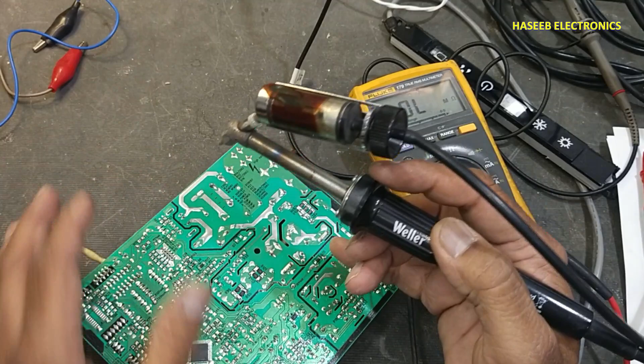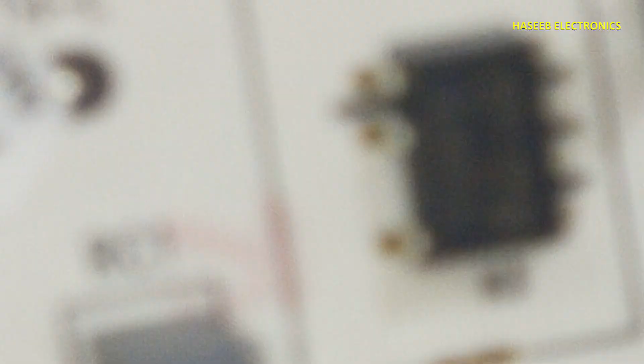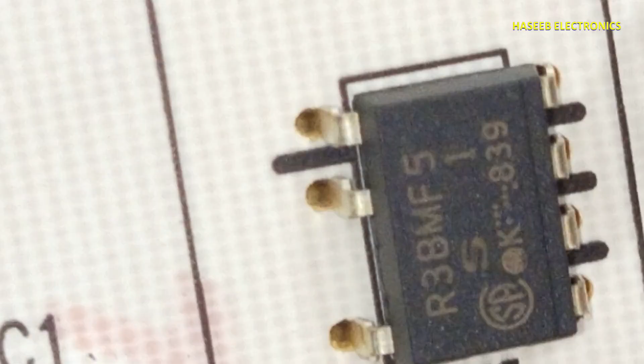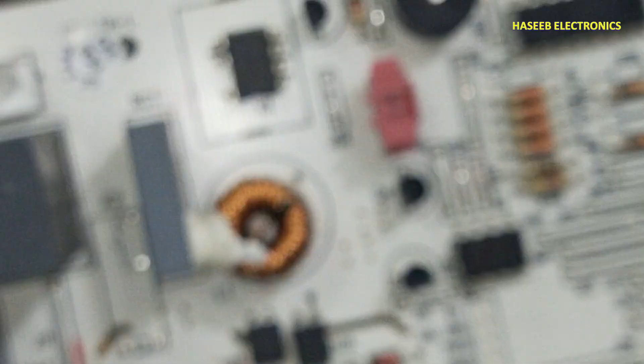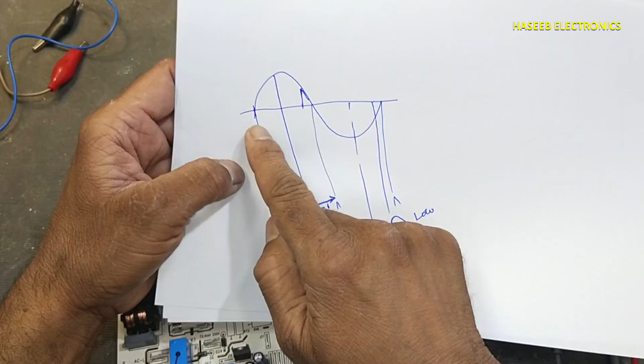And in some conditions, when the fan motor is not running, not spinning up, at that time this solid state relay SSR becomes problematic. That is here. It is R3 BMF 51. So it is a triac based solid state relay.